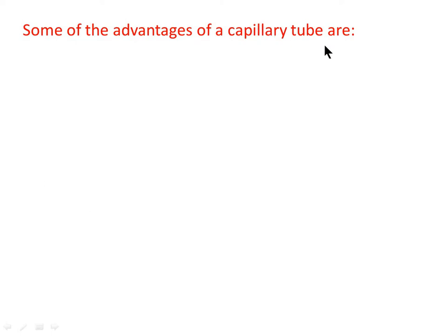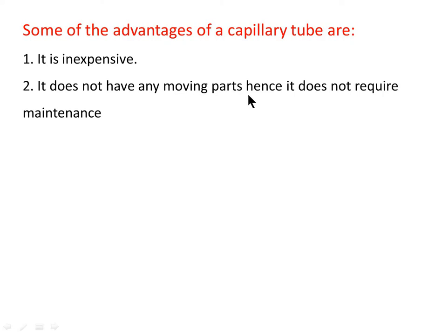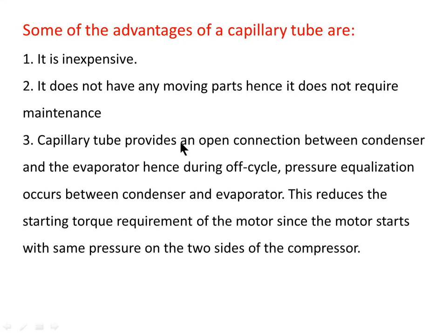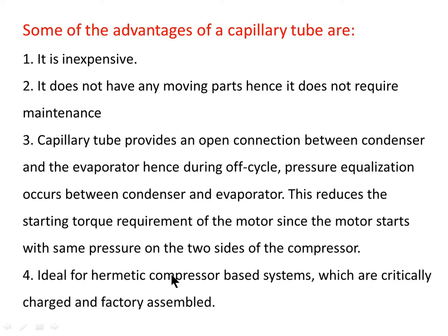Advantages of capillary tubes: they are inexpensive and have no moving parts, hence requiring no maintenance. A capillary tube provides an open connection between the condenser and evaporator, so during the off cycle, pressure equalization occurs between the two. This reduces the starting torque requirement of the motor, since it starts with the same pressure on both sides of the compressor. It is ideal for hermetic compressor-based systems that are critically charged and factory assembled.